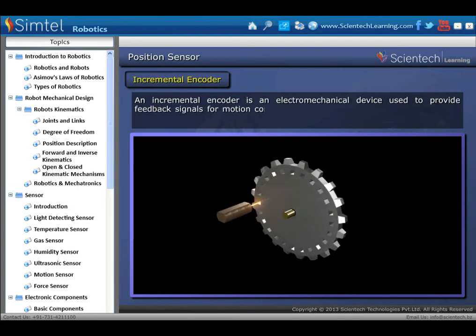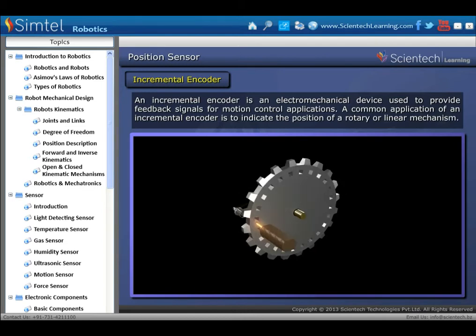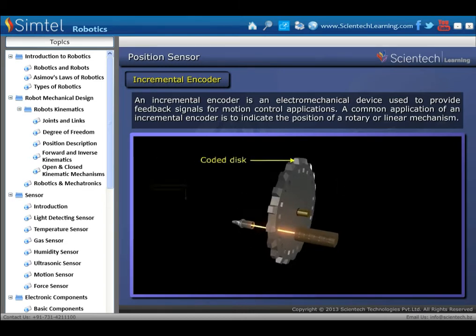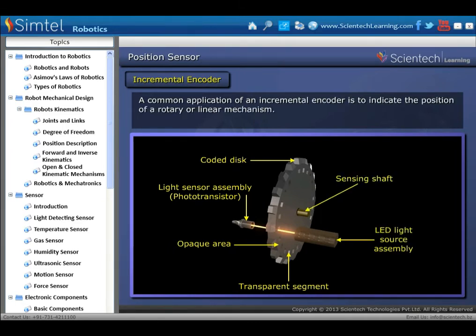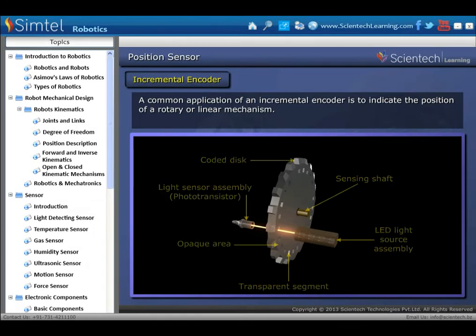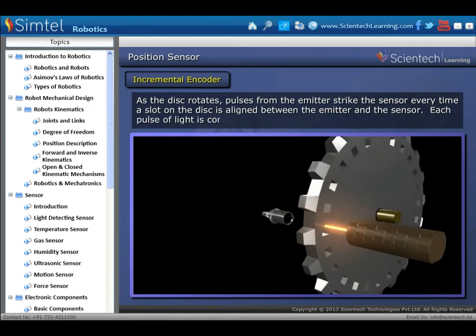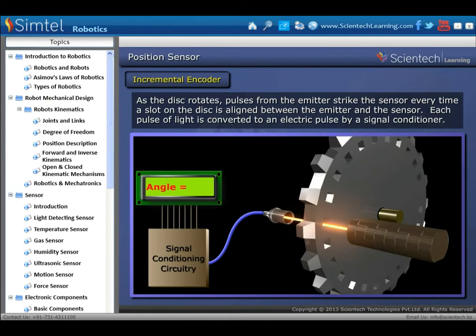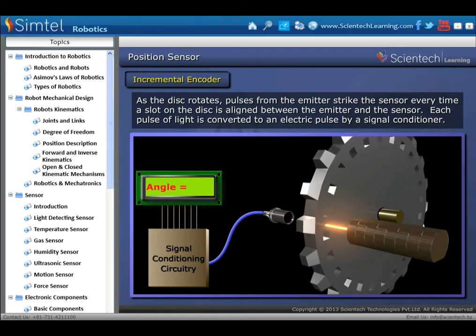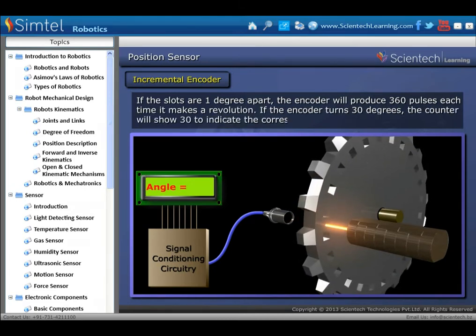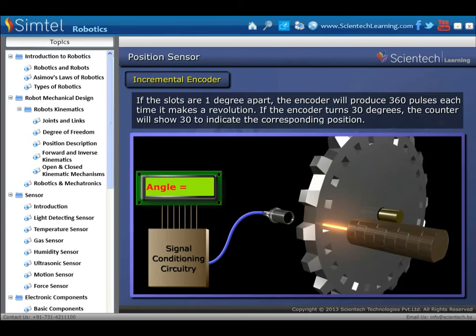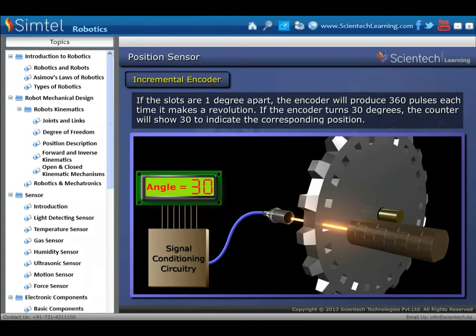First, the incremental encoder: an incremental encoder is an electromechanical device used to provide feedback signals for motion control applications. A common application is to indicate the position of a rotary or linear mechanism. As the disk rotates, pulses from the emitter strike the sensor every time a slot on the disk is aligned between the emitter and sensor. Each pulse of light is converted to an electric pulse by a signal conditioner. If the slots are 1 degree apart, the encoder will produce 360 pulses per revolution; if the encoder turns 30 degrees, the counter will show 30 to indicate the corresponding position.